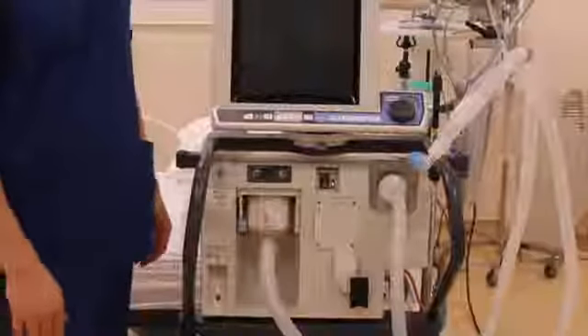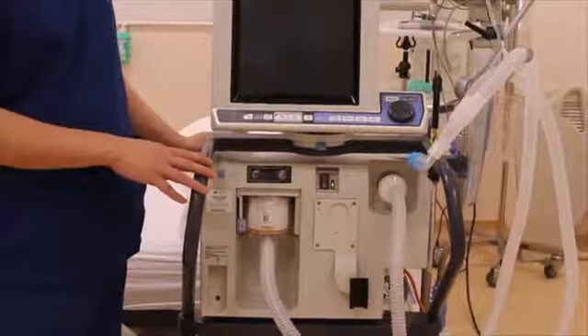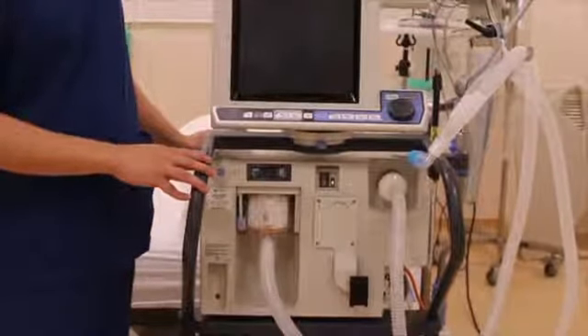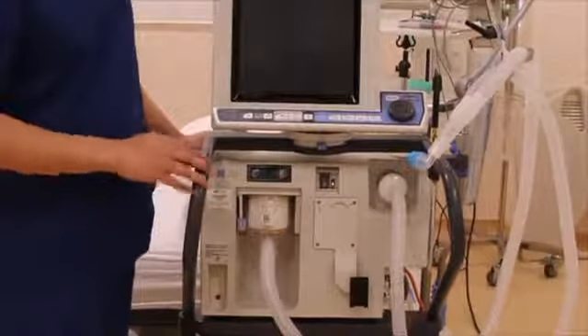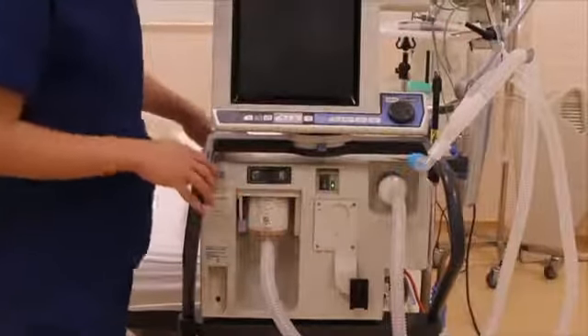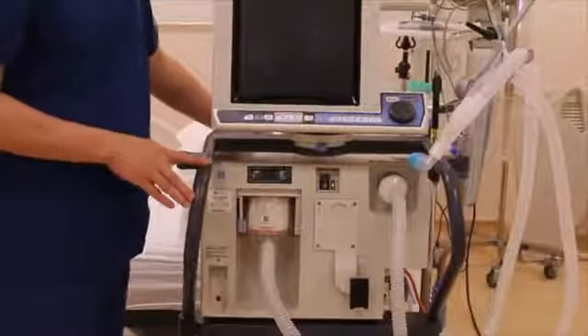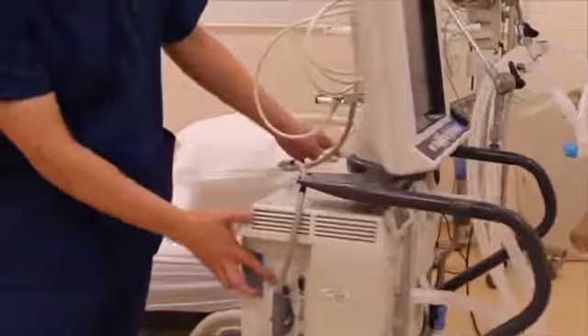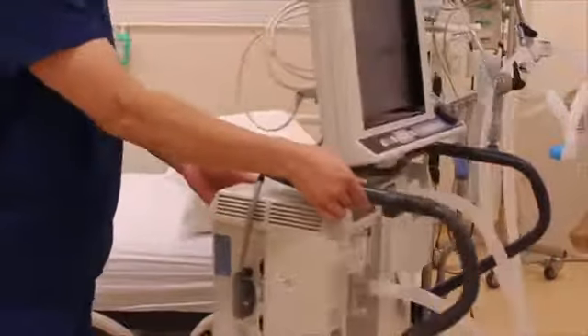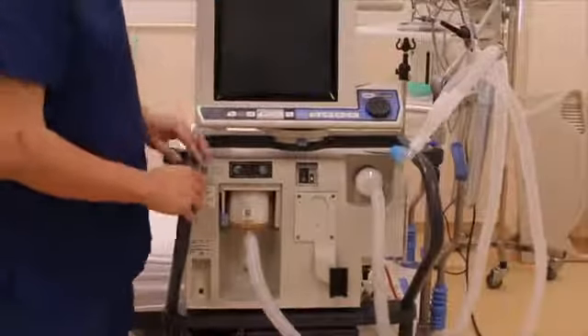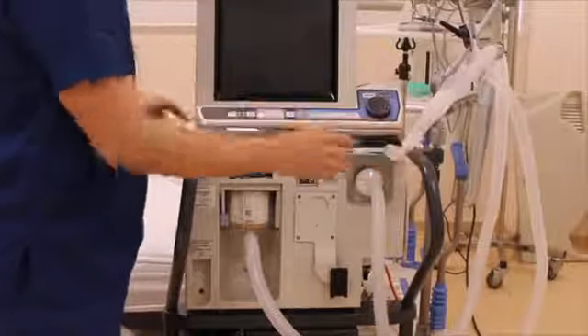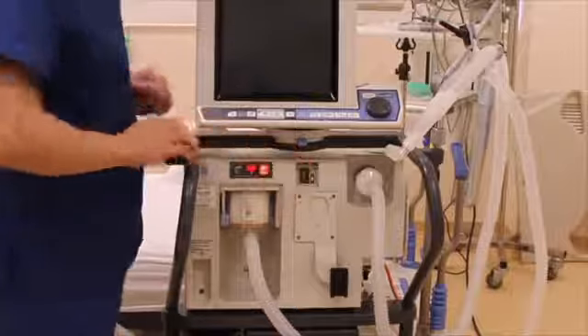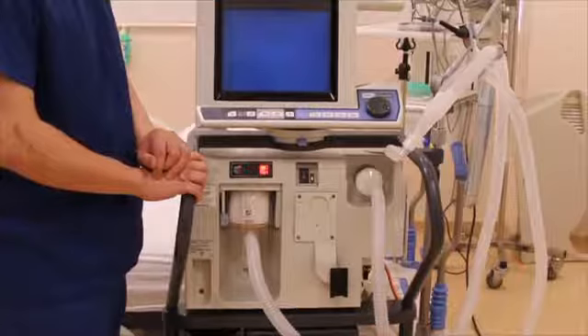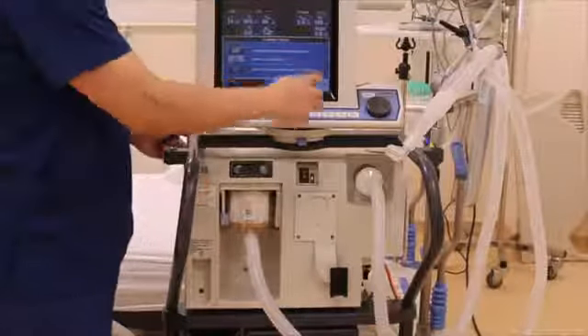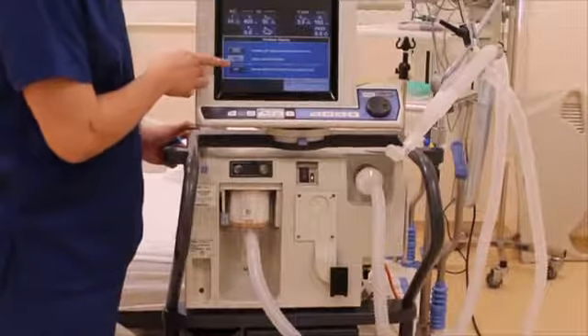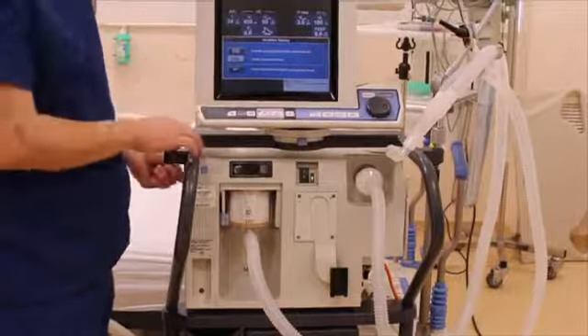Here we'll do a demonstration of the short self test before we connect this mechanical ventilator to the patient. Before we do this step, we must make sure that the inspiratory as well as the expiratory circuits are connected, the power plug is plugged in, and the gas supply is connected. For this SST, we need to also be aware of the button that we need to press when the option for SST is shown, which I will demonstrate later. Before we proceed, remember to remove the cap from the circuit wye limb before we power on the switch. After the welcome screen has been shown, you will have an option to perform the SST. So when that button is pressed, I will at the same time activate the test button at the side, which I have shown to you earlier.